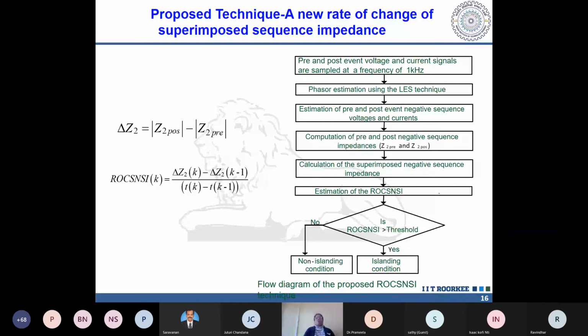At the terminal of the renewable sources, we calculated the pre and post voltage and current signals at a sampling frequency of 1 kilohertz, with phasors estimated by the LES technique, least error square based technique, used for phasor estimation of the digitized instantaneous voltage and current signals. Then we estimate the pre and post negative sequence voltage and current from there, since LES calculates the phasors VA, VB, VC, IA, IB, IC, and from these phasors we calculate the negative sequence components like V2 equals VA plus A VB plus A square VC, over 3.